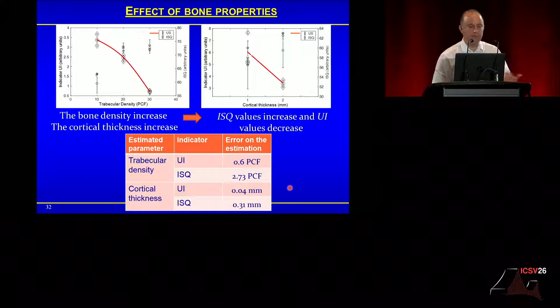Same thing regarding cortical thickness variation. Here is 1 millimeter cortical thickness, 2 millimeter cortical thickness. The implant is more stable here, so it's normal. You have a decrease of the ultrasonic amplitude coming back from the implant, and in the case of the resonance frequency analysis, you have a small increase. Standard deviations were not great in this case. Again, we could compare and show that we can retrieve the cortical thickness with more precision using ultrasound than using ISQ.